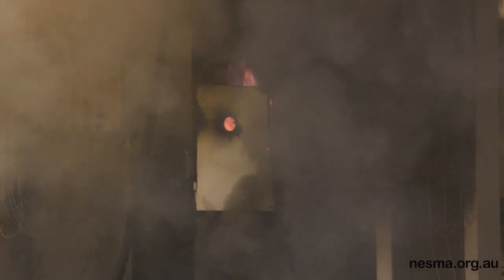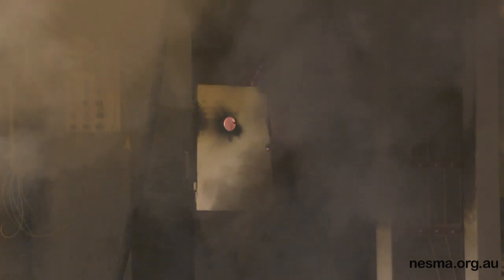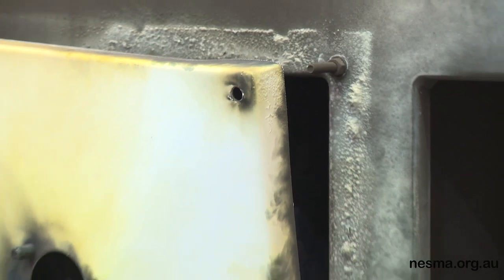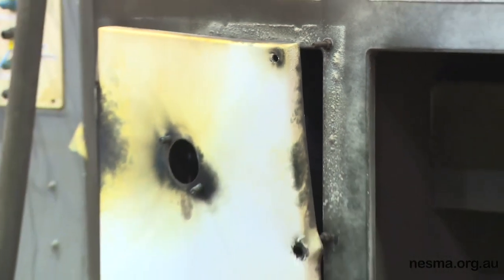One thing to remember is that to ensure that the fault stayed on the line side, in this particular example, the circuit breaker was left in the off position, so there was no engagement between the operating shaft and the handle. So that meant the only thing that was holding the handle on to the front cover or the door were the small securing screws, and they're only quite small.